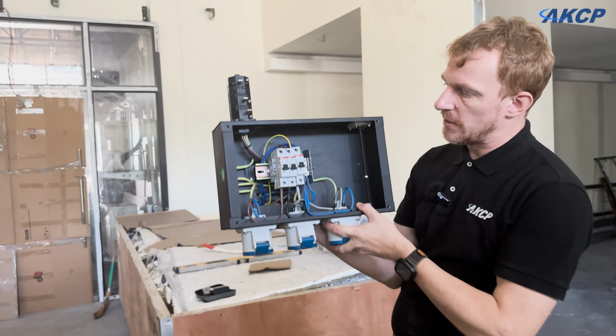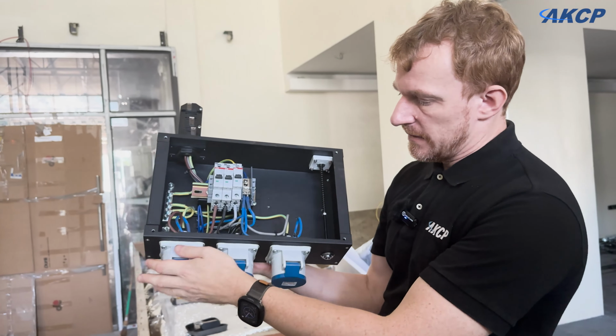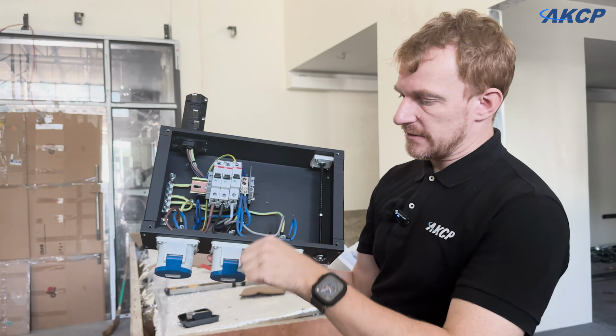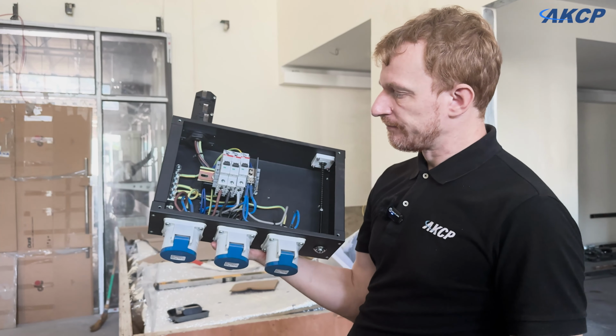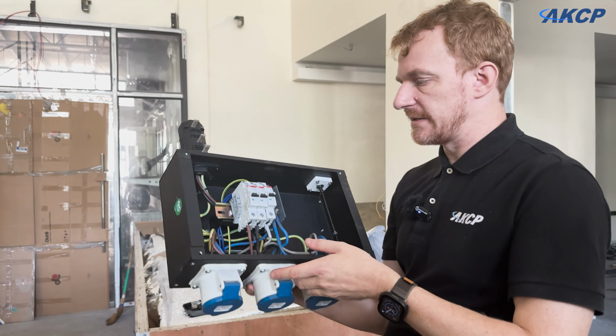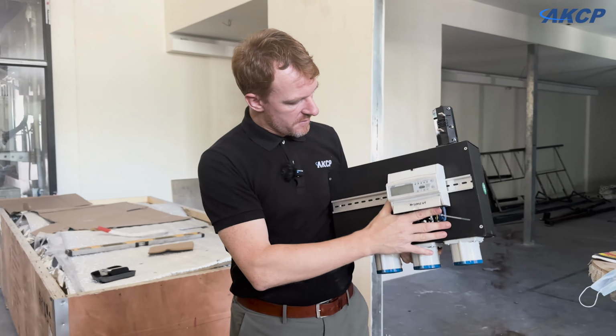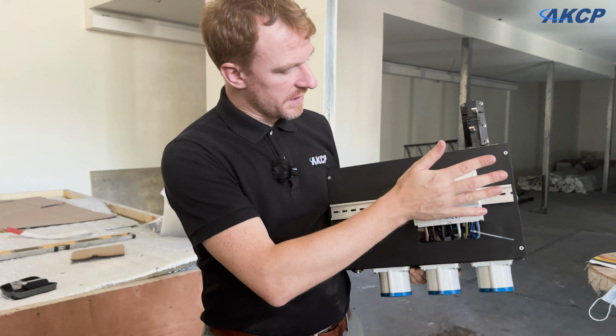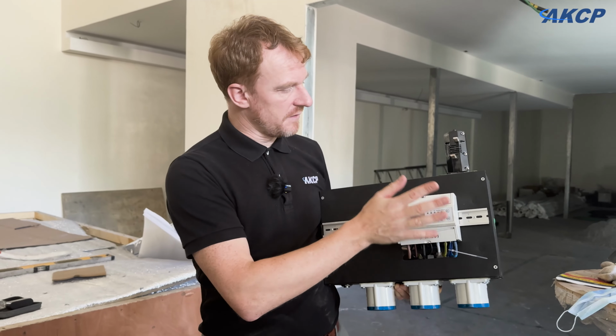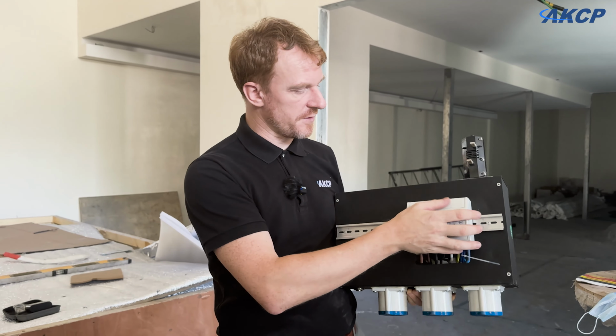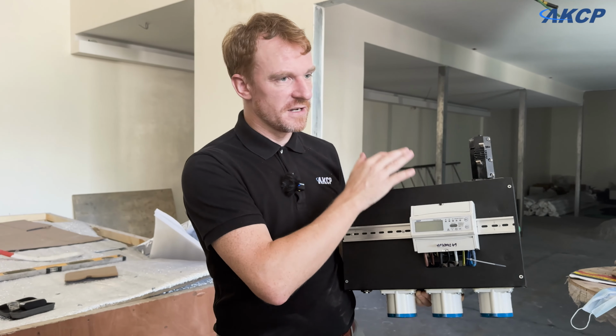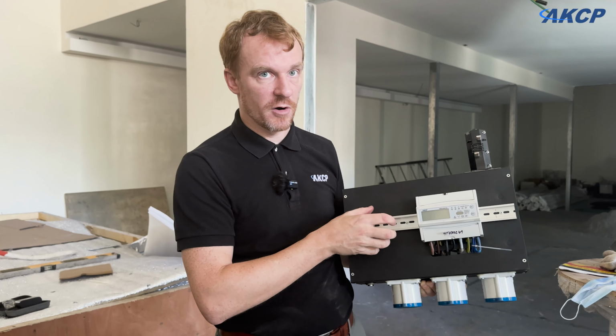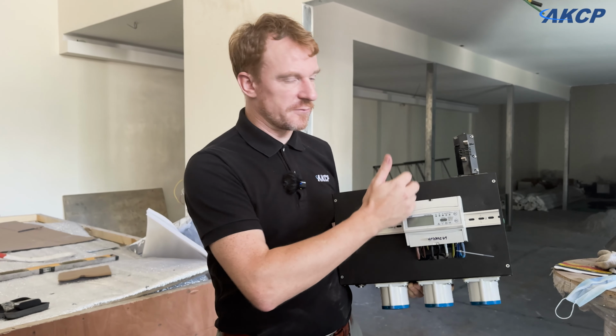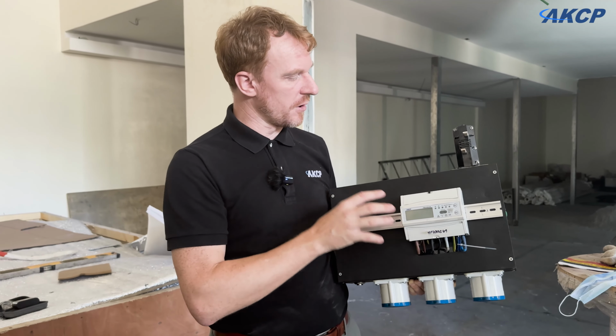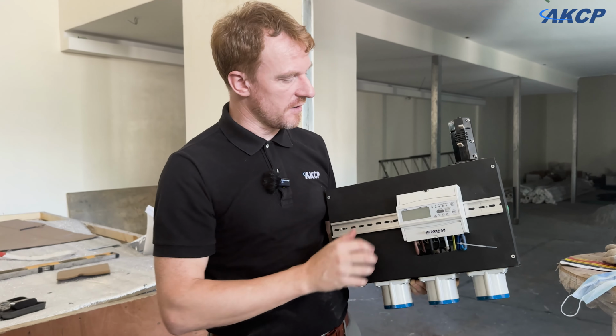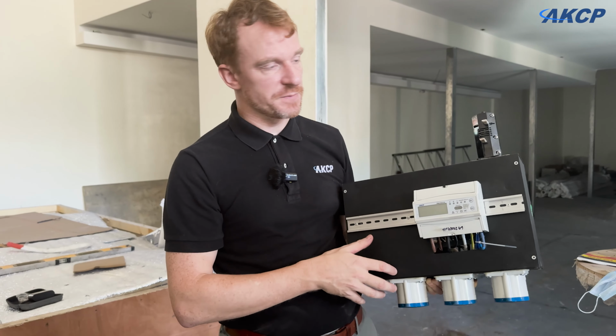So on every one of these overhead boxes, we have 3 single-phase sockets, which go to our heaters, plus the 3-phase socket for the fans. On the back of this, we've installed a DIN rail, and we're putting a power meter on here. This power meter will be 1 per rack, and then we'll have an SP1 Plus, which will handle 3 or 4 racks in a row. So we can put them in series. These are Modbus RS485 back to the SP1 Plus.